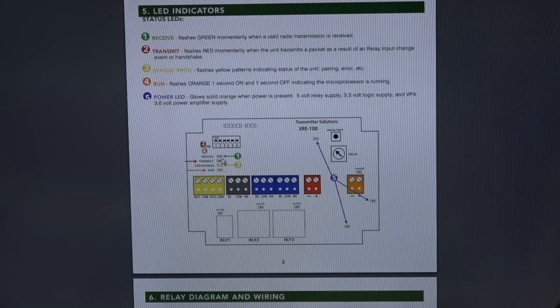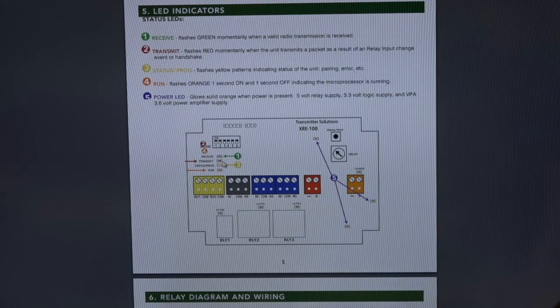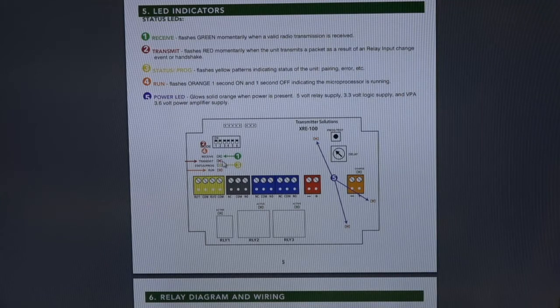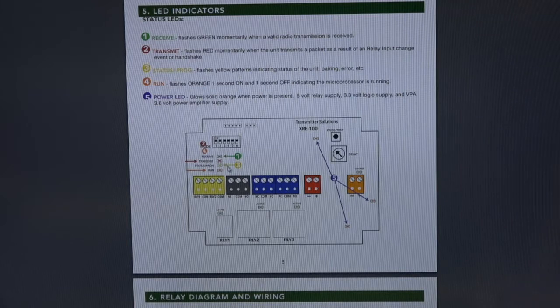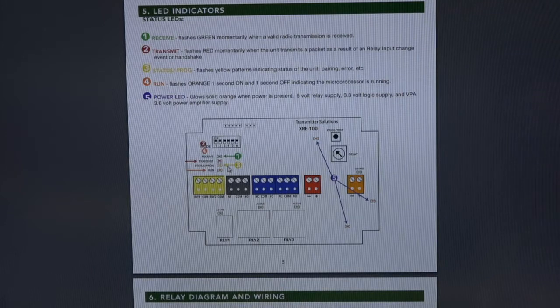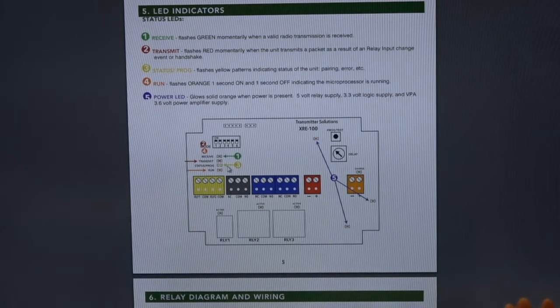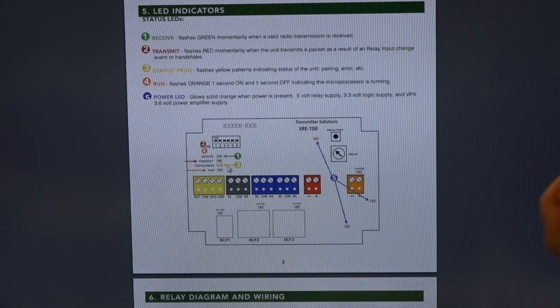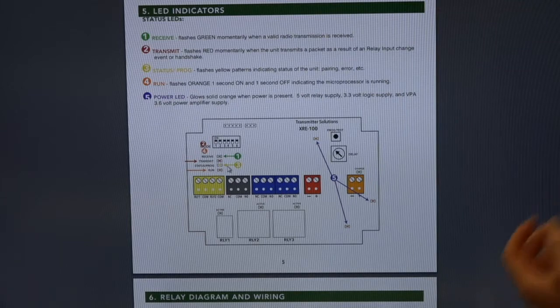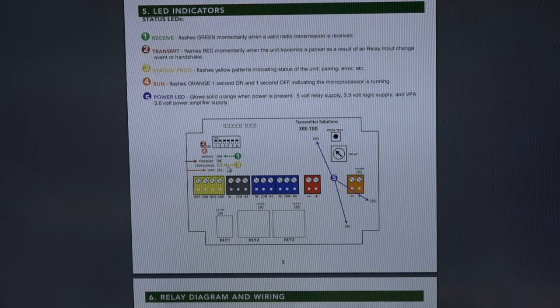Green is a receive light when the transmission is sent and I'll show you all this in real time. Red is a transmit light for when our input closes and sends a signal. Yellow is a status or program light, which is used for programming. But also our units are checking in with themselves every 15 seconds. So that if something was missed or something has changed, that they automatically fix themselves after 15 seconds. They're always checking in every 15 seconds to make sure they're in the right state. Open, closed, whatever it may be, we want to make sure they're in the right state.